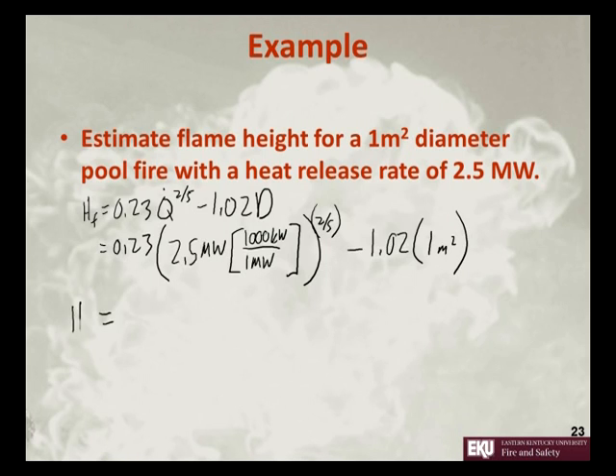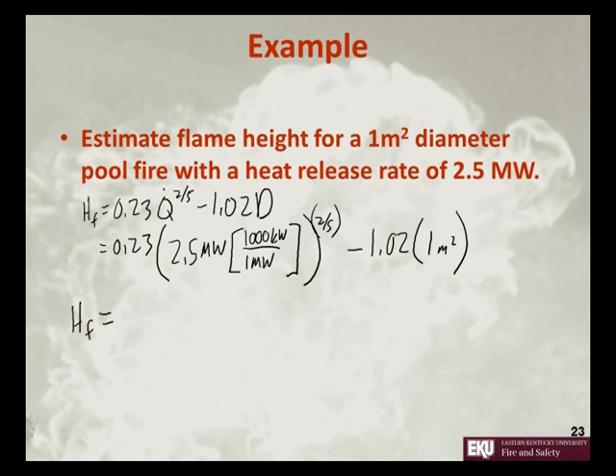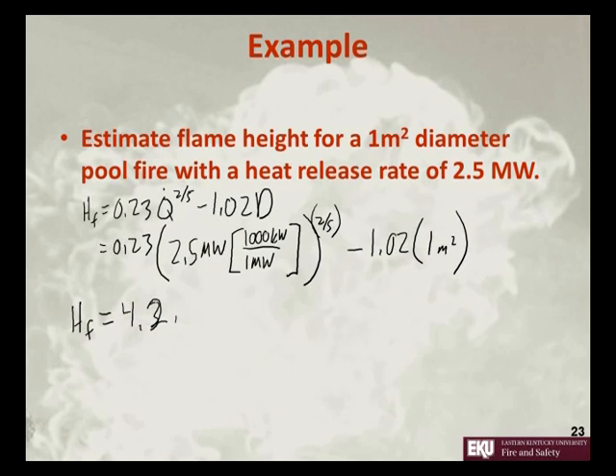So this is equal to 0.23 times 2,500, raised to the power of (2 divided by 5), minus 1.02 times 1. This gives us a flame height of approximately 4.2 to 4.3 meters.